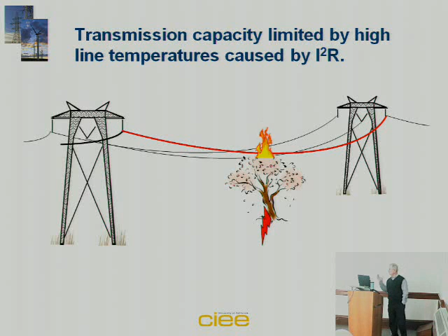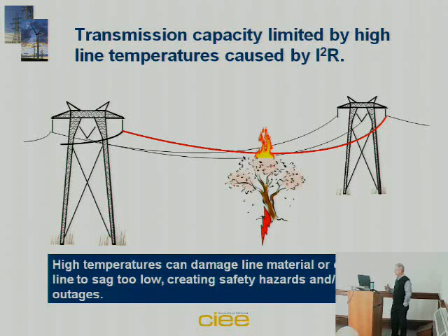And so we, at the moment, need to limit the amount of current that can flow through these lines. And high temperatures can both damage the line material if it gets hot enough, and so you have to replace the line, or more likely can cause the line to sag too low, and this creates safety hazards and/or outages.